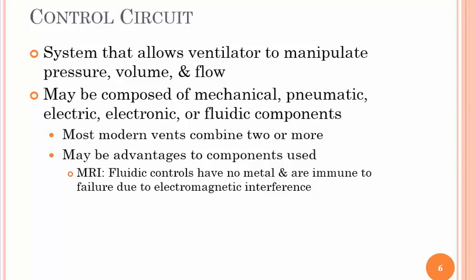Most modern day ventilators combine two or more control types, and there may be advantages to the components used. For example, if you have to take a ventilator into MRI, you can't have any metal in it because of that giant magnet. Fluidic controls have no metal in them, so they would be the type you'd want to use. Most of them will say MRI compatible.